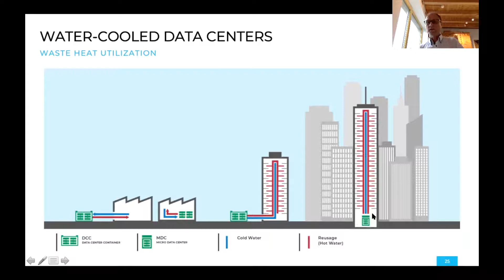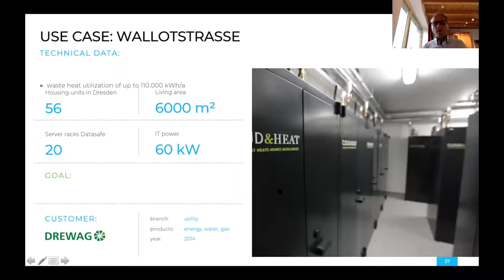This is an apartment building built 5 years ago in Dresden, with 56 apartments. In the cellar, we placed our servers with our heat recovery technology. You see the piping here - this is all liquid piping. We let in a little air, but the rest is really direct water cooled. These 56 apartments are basically heated with the waste heat of these servers, which we did together with a local energy provider.